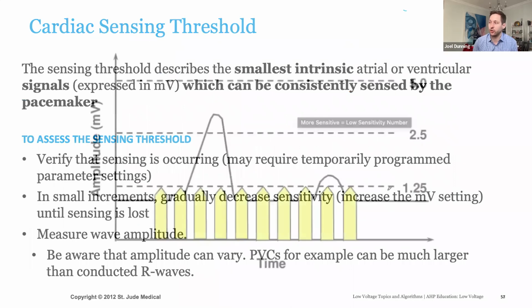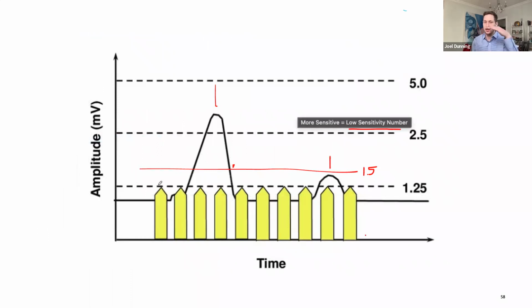Basically, your sensitivity threshold is this fence here, and that's the best way to picture it, as a fence. Your goal is to not see what's happening here with the T wave, but you still want to see what's happening here with the R wave, right? So you have to raise your sensitivity value so that it's above the T wave. In this case, if you have your sensitivity set at 1.25, you are very sensitive. So the device will see every signal that is above 1.25 millivolts. In this case, that's both the R and the T. By raising your sensitivity program setting, you can effectively miss what's occurring here. You don't oversense the T waves, but you're still properly sensing the R waves. That way the device can respond accordingly and inhibit pacing when it needs to, and pace when it doesn't.